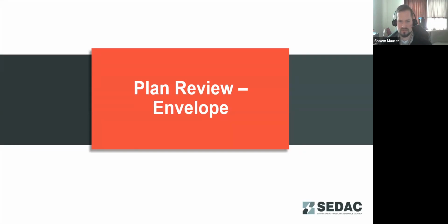As far as what's required on the construction documents, looks like most people got most of this information correct. The U factor, solar heat gain coefficients, mechanical system design criteria, and air sealing details are all required on those construction documents. The other information is not required, but is often helpful to have there. So now I will turn the presentation over to my colleague Ryan Siegel to continue on.